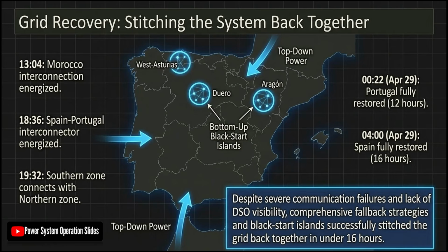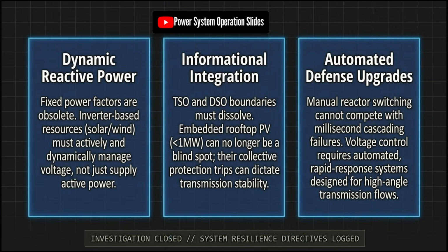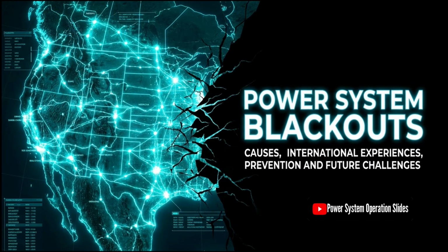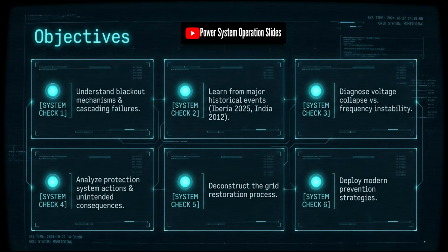At the same time, voltage stability and reactive power availability are becoming increasingly important. A system may maintain acceptable bus voltages under normal conditions while having a very small voltage stability margin (VSM) to voltage collapse. Heavy power transfers, transmission constraints, inadequate reactive reserves, generator reactive power limits, and high penetration of inverter-based resources can significantly reduce this margin. Consequently, monitoring only voltage magnitude is insufficient. Operators increasingly need to assess the system's proximity to its stability limits.